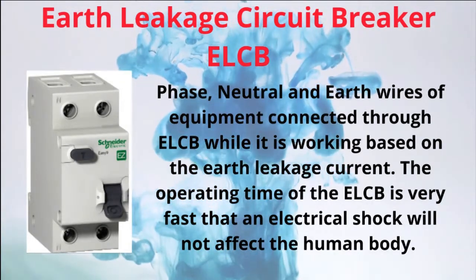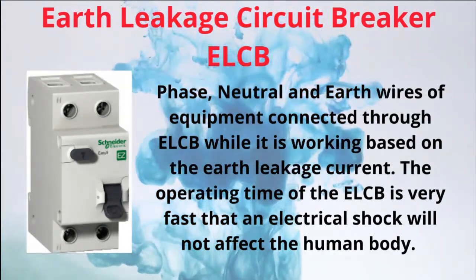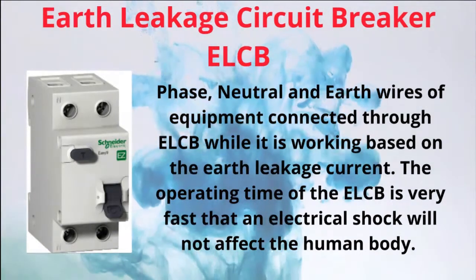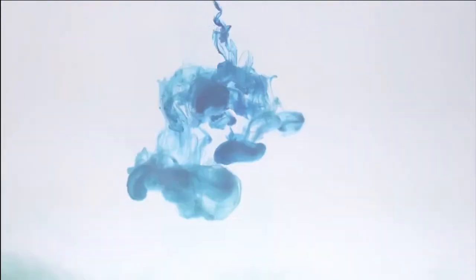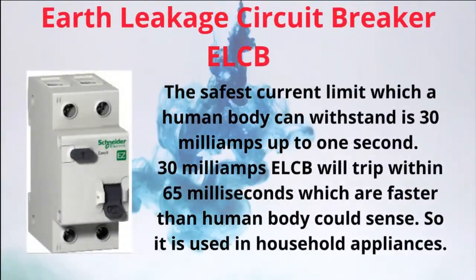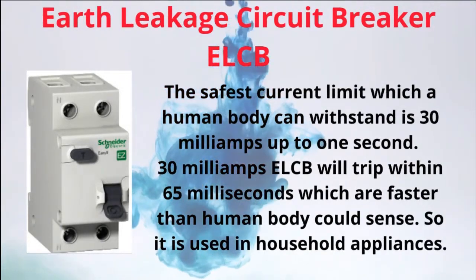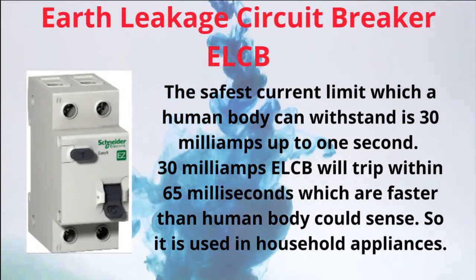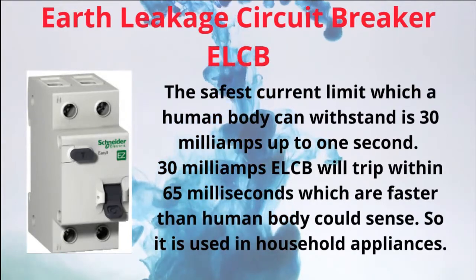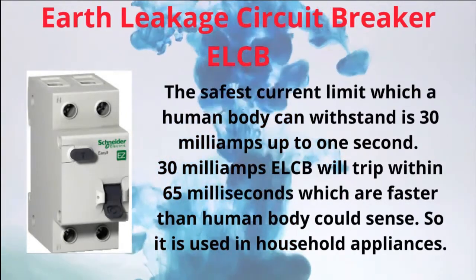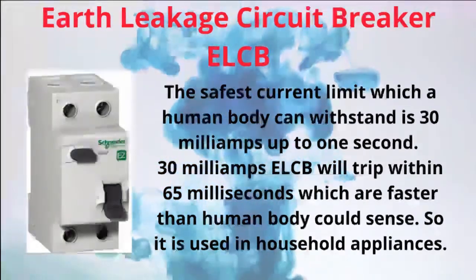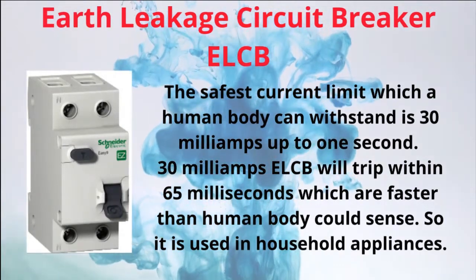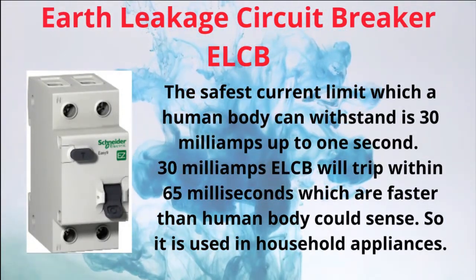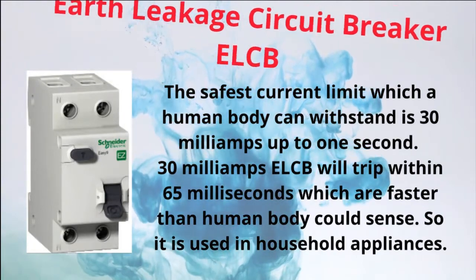The operating time of the ELCB is so fast that an electrical shock will not affect the human body. The safest current limit which a human body can withstand is 30 milliamps up to 1 second. A 30 milliamp ELCB will trip within 65 milliseconds, which is faster than the human body could sense. So it is used in household appliances.